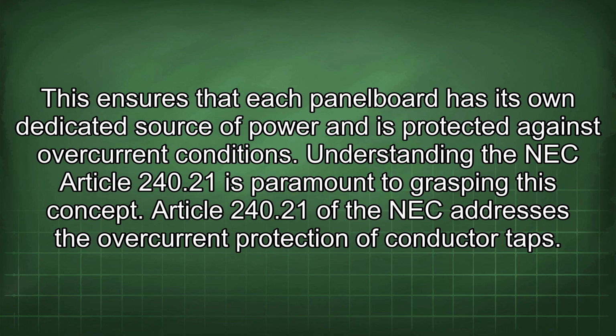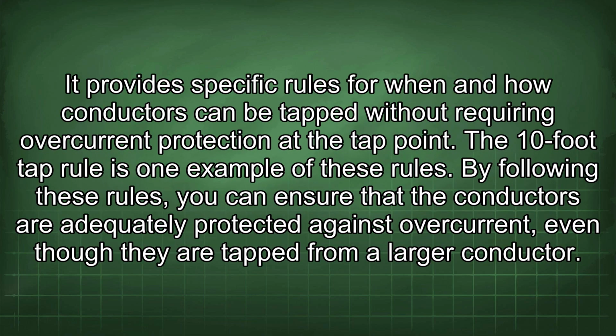Article 240.21 of the NEC addresses the overcurrent protection of conductor taps. It provides specific rules for when and how conductors can be tapped without requiring overcurrent protection at the tap point. The 10-foot tap rule is one example of these rules.